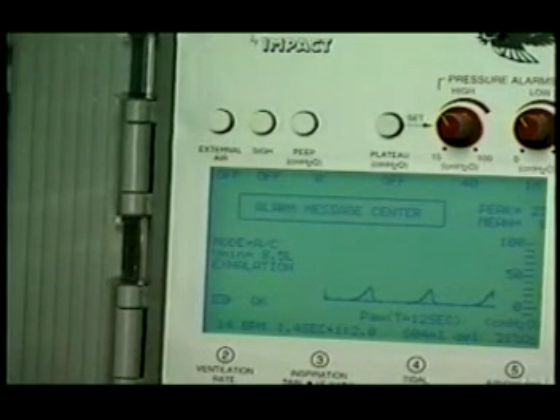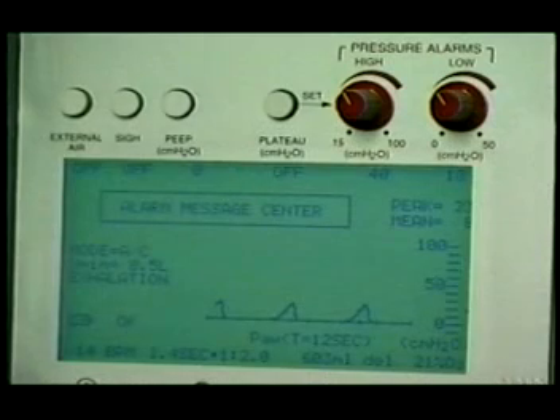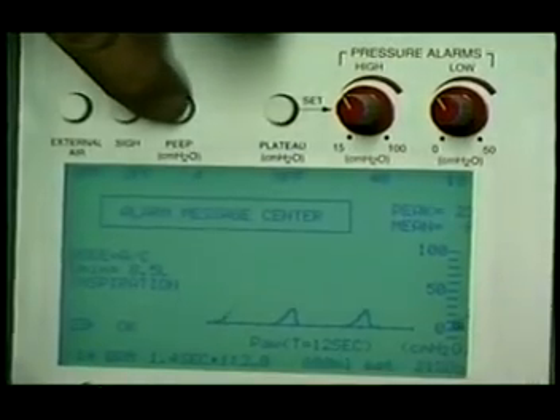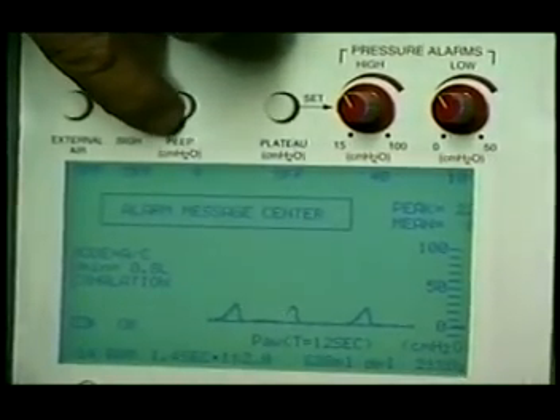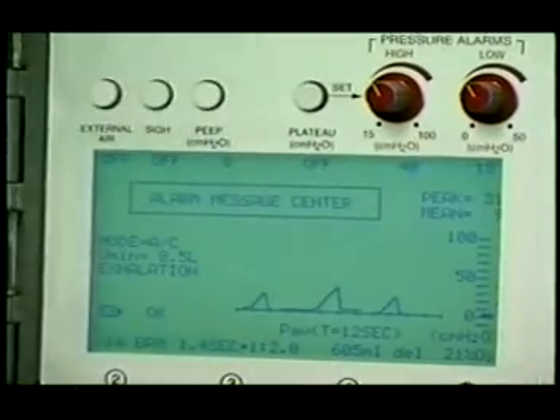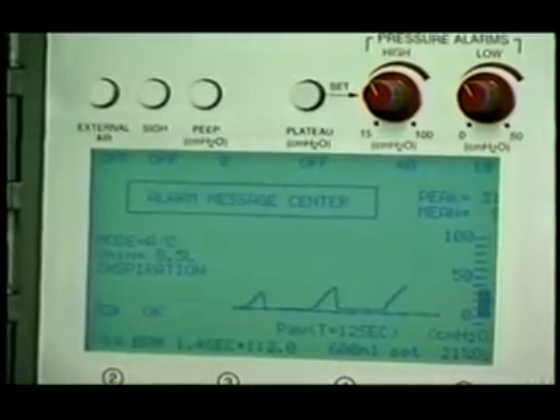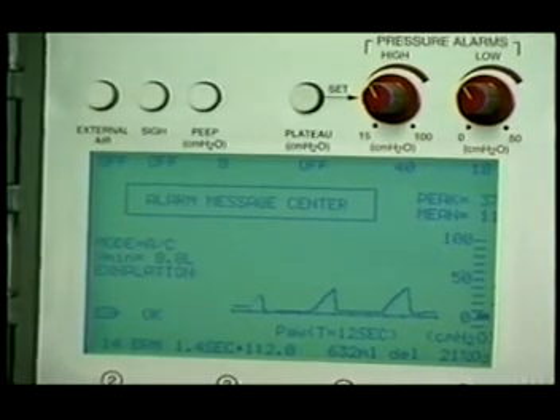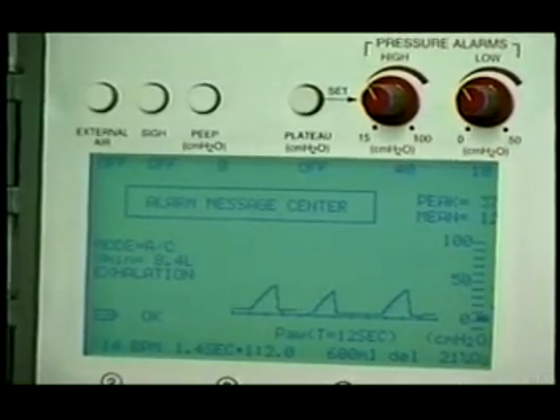After setting the 5 primary controls, you may decide to use other operating features. Secondary controls have automatic or standard defaults. Others are adjustable. You can add PEEP, set low and or high pressure alarm limits, use external air, or select operation with sigh or pressure plateau. Setting PEEP is simply a matter of pressing the push button, which causes the PEEP value to increase each time the push button is pressed. As PEEP develops within the ventilator circuit, the LCD waveform and digital bar graph display this remaining positive pressure.